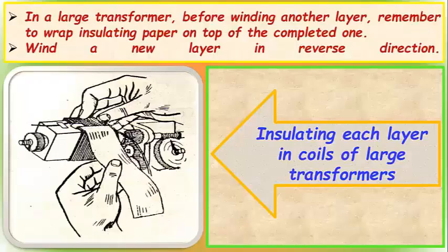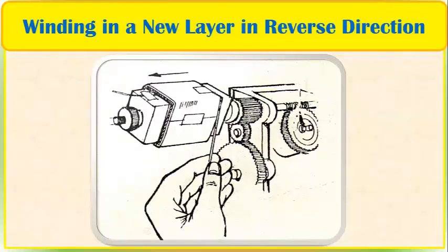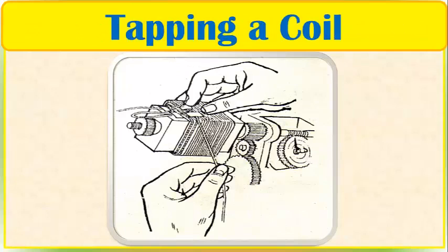In a large transformer, before winding another layer, remember to wrap insulating paper on top of the completed one. Wind a new layer in reverse direction. So this is insulating each layer in coils of large transformers, then winding a new layer in reverse direction. To tap a coil, make a loop of the magnet wire about 4 inches long. Extend it outside the bobbin and continue winding. The procedure in the coil tapping is the same for small and large transformers.